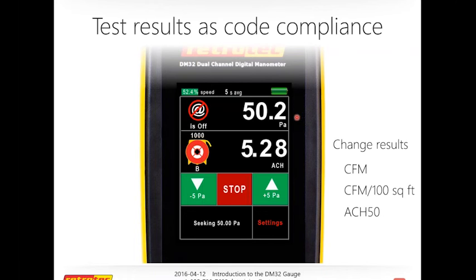the gauge is going to tell the fan to stay at 50 pascals to maintain it no matter what. So if anybody is, say, stepping on the hose, walking in front of the fan flow, opening up the door, the fan is going to speed up and speed down. It's going to try its very best to maintain 50 pascals.